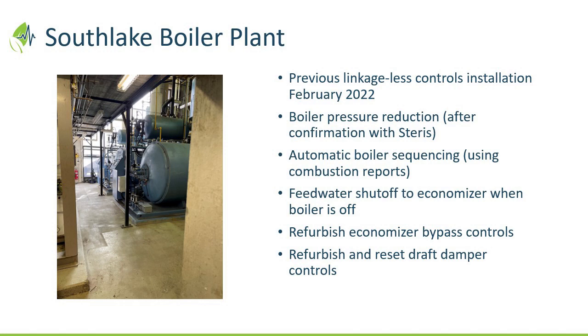So pressure, flow, and on the exit, it's the same. And we're in a climate here in Canada where we have very significant seasonal change. And so you can measure and control input all day long, but if you don't control the draft on that boiler, you lose the ability to maintain that tight gas-air ratio just through draft, right? So now you're drawing through the boiler. So every time you add excess air to combustion, you actually decline in efficiency. So that's just a bit of an overview on how linkageless works, why draft and pressure is important. Input-output control is just as important as anything else. Let's pass that to John for a moment. You've been there, done that.